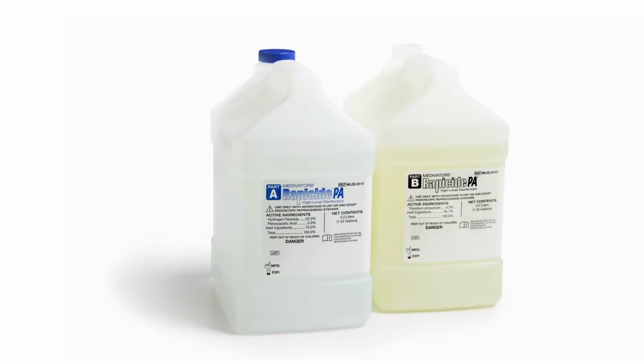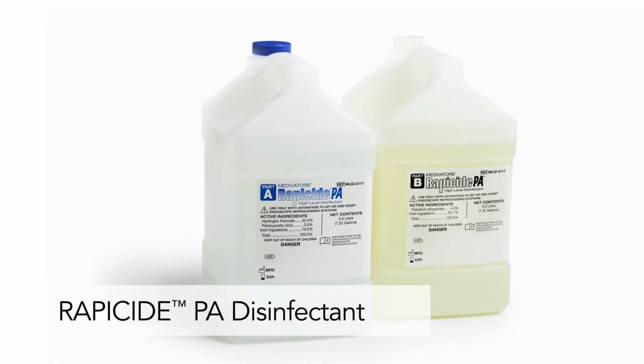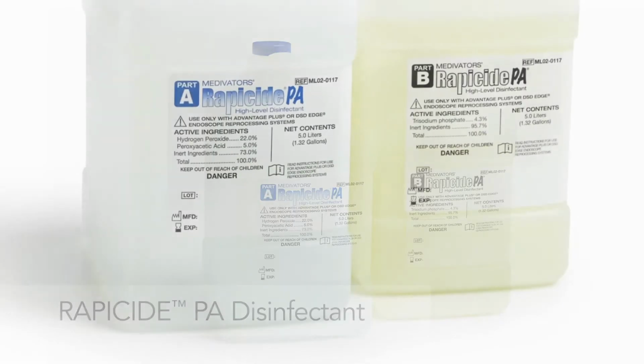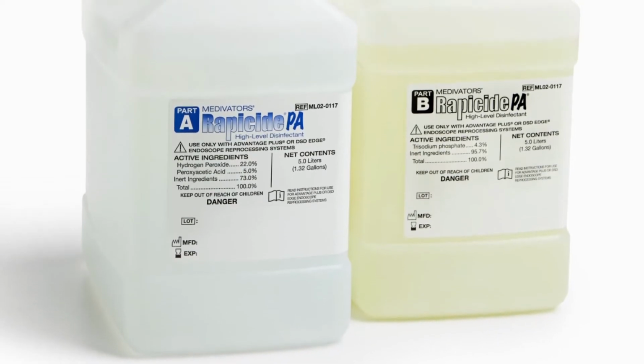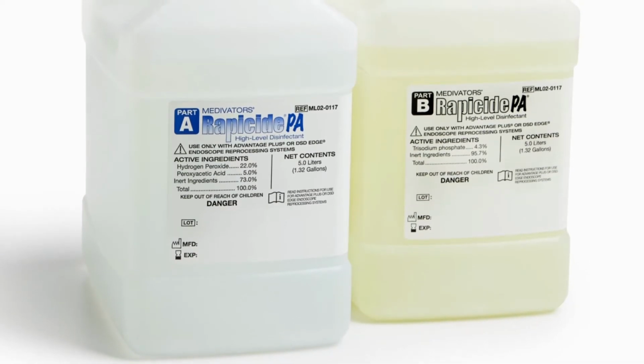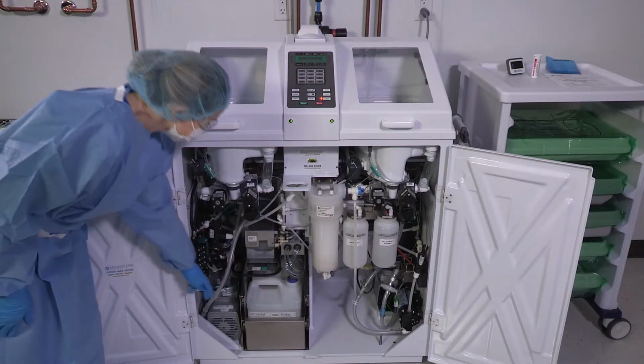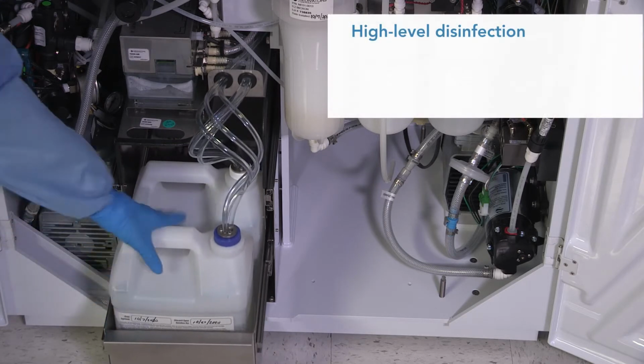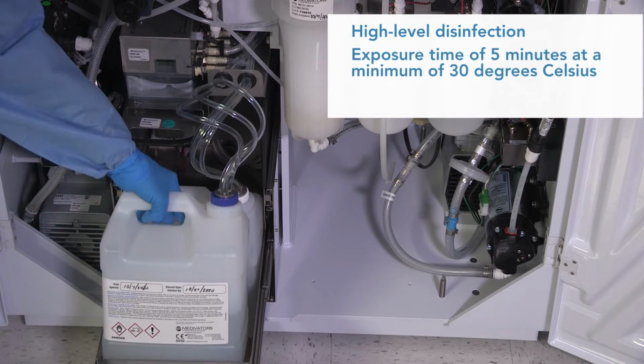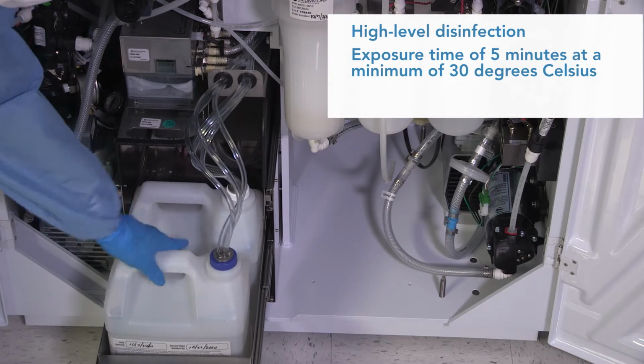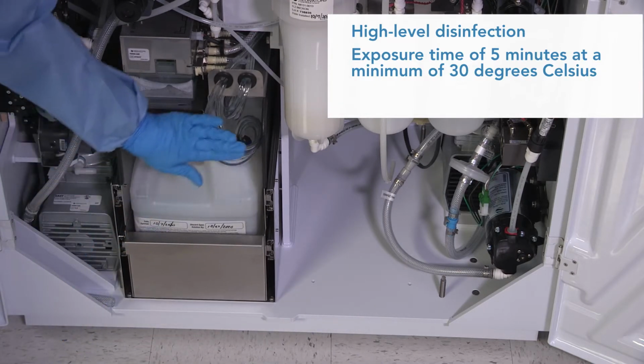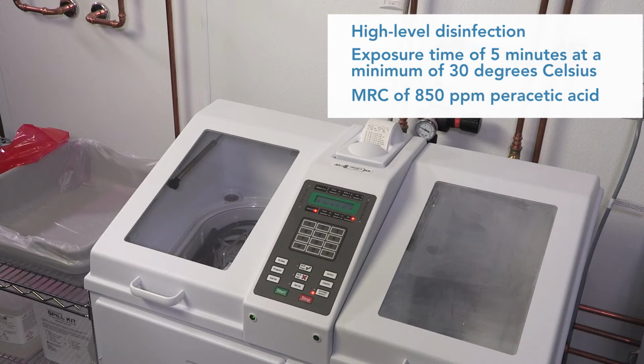The DSD EDGE Reprocessor uses Rapicide PA disinfectant, which comes in 2 parts, A and B. Rapicide PA disinfectant is a single-use peracetic acid-based solution with proven materials compatibility. Rapicide PA disinfectant achieves high-level disinfection with an exposure time of 5 minutes at a minimum of 30 degrees Celsius, at a concentration equal to or greater than the minimum recommended concentration, MRC, of 850 parts per million of peracetic acid.